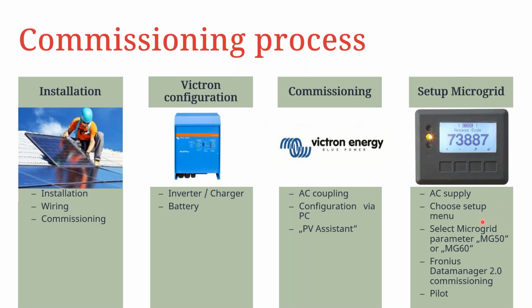to the inverter. You have to select the country setup, and in this case, we talked about the MG50 or MG60. And this kind of microgrid setup can be done with both data manager-based inverters as well as pilot-based inverters. So all the Symo inverters from 3 kilowatts up to 27 kilowatts from Fronius are fitted with the data manager, and the Tauro inverter and the Gen 24 Plus inverters are fitted instead with a pilot communication module. So both those two inverters can be used for microgrid setup.